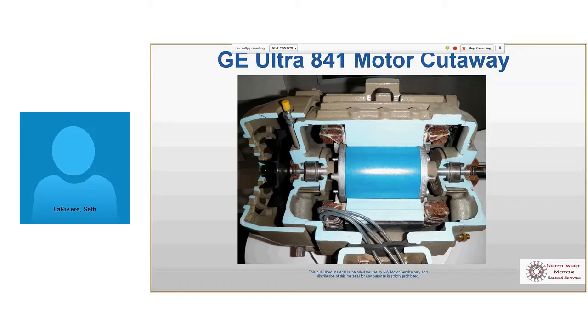What on that cutaway shows that it's rated vertically? So let's talk a little bit about vertical applications, because there are some considerations we have to make. For GE, at about 75 horsepower, that's when the weight of the rotor starts to become excessive for what the bearings can handle. So if your belt drive, shaft up or shaft down, doesn't really matter, all the weight of that rotor is hanging on those bearings, right?